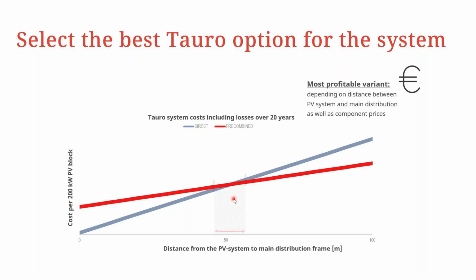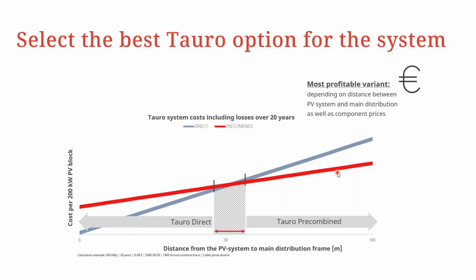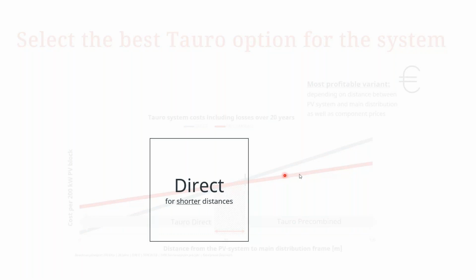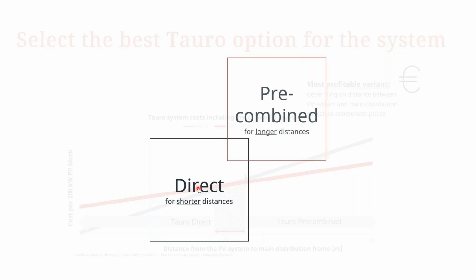We have an equilibrium point at the 50-meter mark. So for direct systems, if you're not going beyond 50 meters, the direct topology turns out much more economical. But if you go beyond the 50-meter mark, the pre-combined topology becomes much more economically viable. To summarize: for short distances, go direct; for longer distances, go with the pre-combined version.